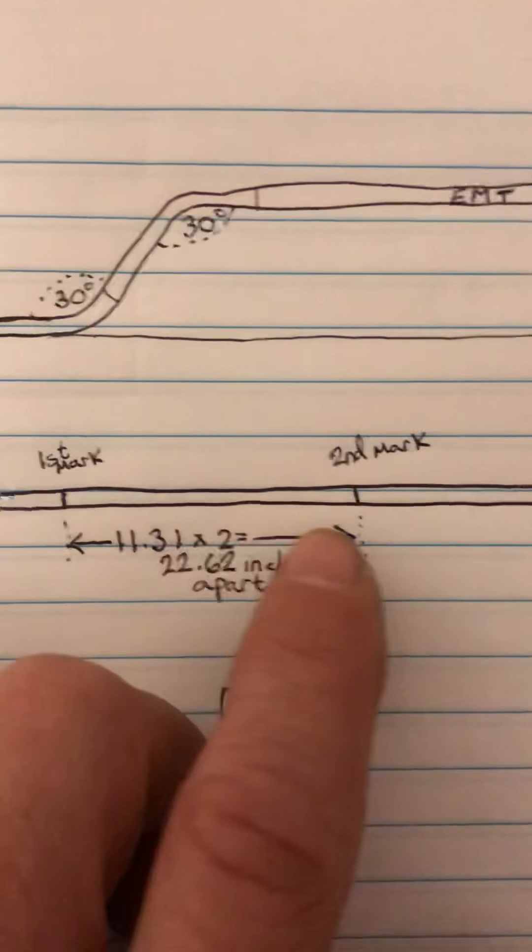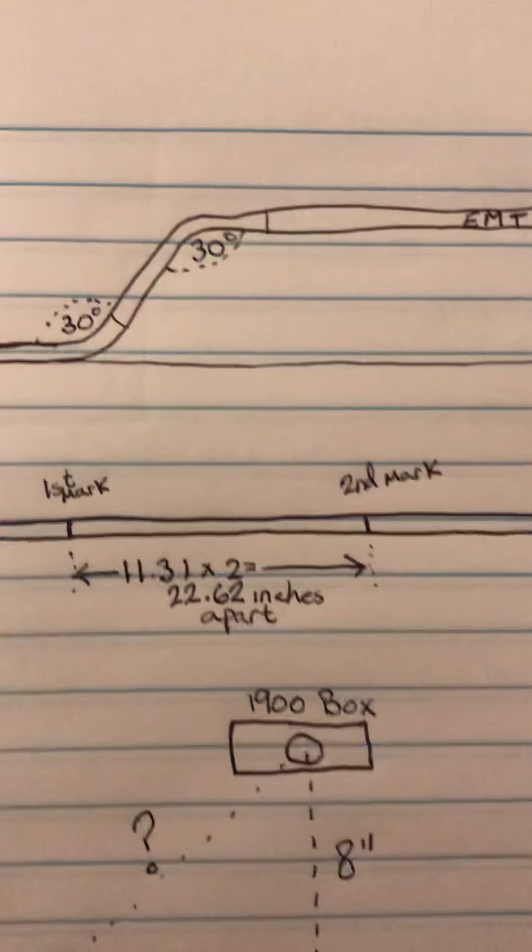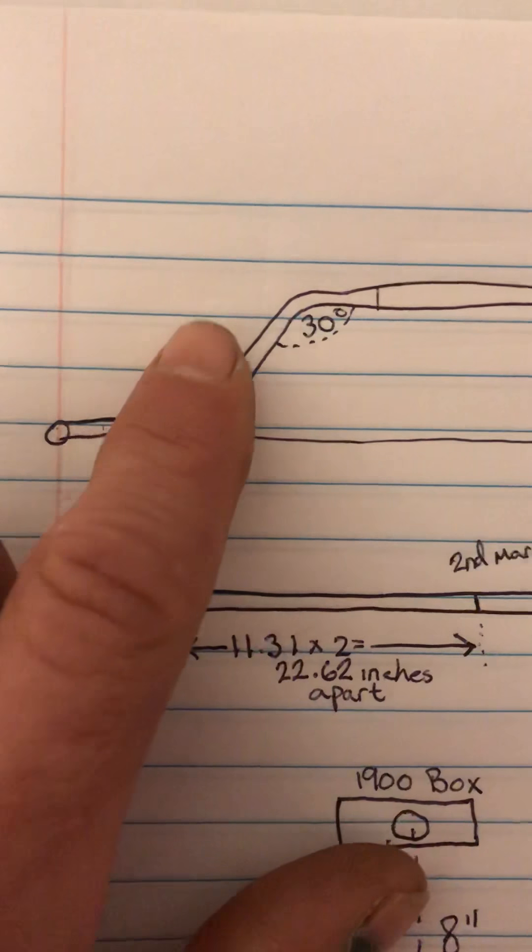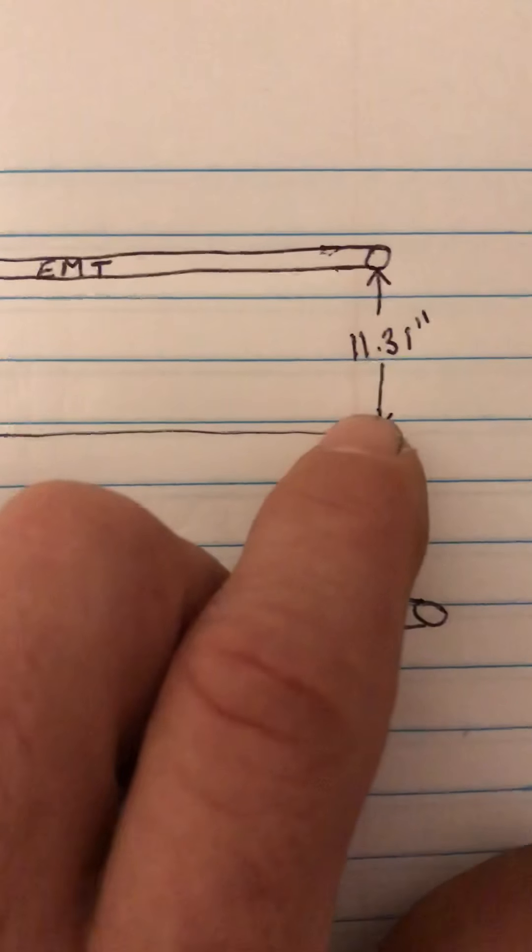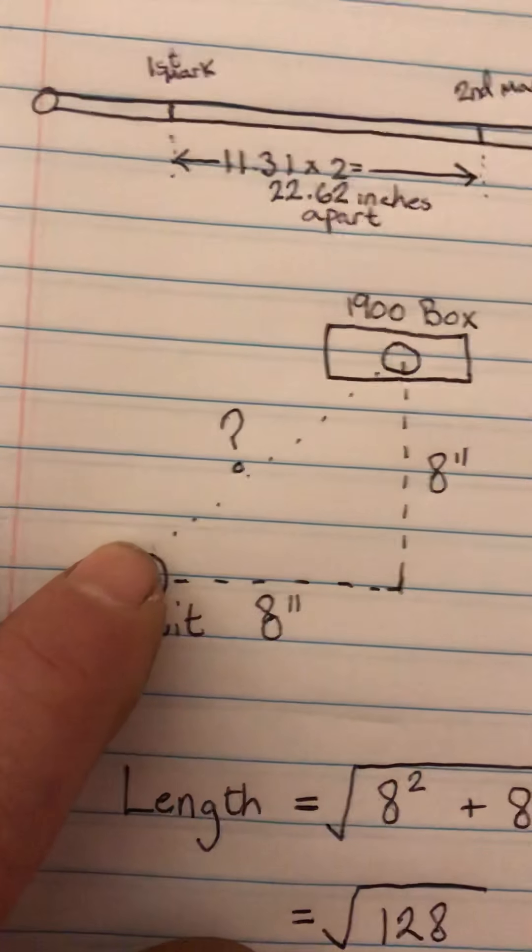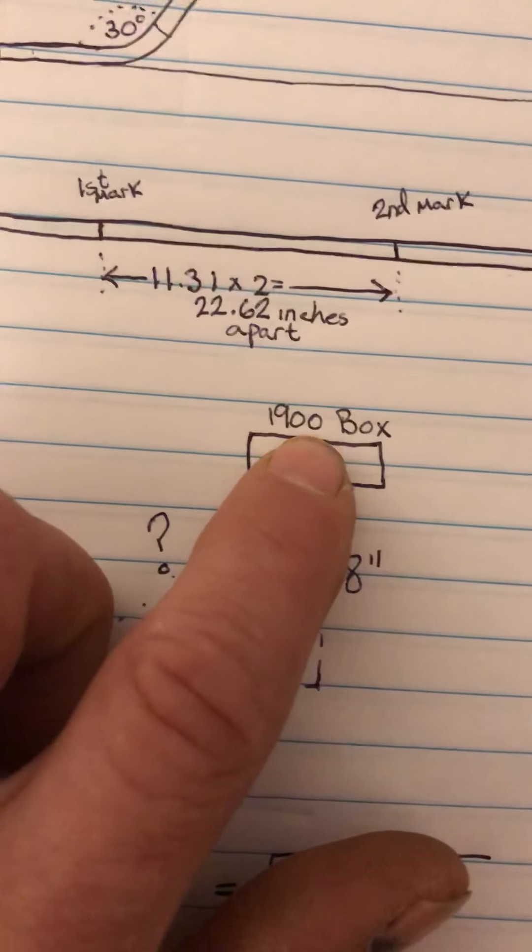The marks have to be 22.62 inches apart. Then once we bend it - our 30 degrees here and our 30 degrees here - we will come up with the 11.31 inches that we need to get this conduit from where it's at now to that 1900 box opening.